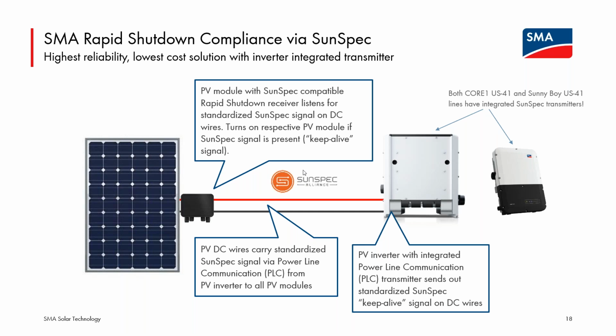Again, the SunSpec Alliance published their power line communication protocol. So it's an open standard that anyone can build products that comply with, and they can then submit those products to the SunSpec Alliance for testing. That is what SMA has done. So the transmitter boards in our CORE1 US-41, as well as our Sunny Boy line, have been certified by the SunSpec Alliance to be in compliance with their open standard. So the transmitter is in the inverters for the SMA system.